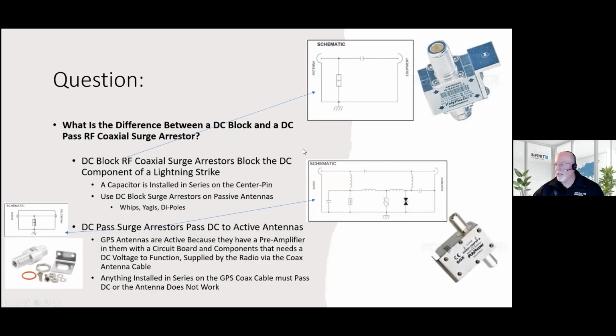If you have an active antenna, like a GPS antenna that has a preamplifier in the antenna, so there's a circuit board in there with components that requires a DC voltage to operate, and that voltage is transferred to the antenna by the receiver through the coax cable, then anything you install in series on the coax cable has to pass that voltage, or the antenna is useless. So you need a DC pass surge arrestor for, like, GPS timing signaling equipment, for example. You would have to have that.